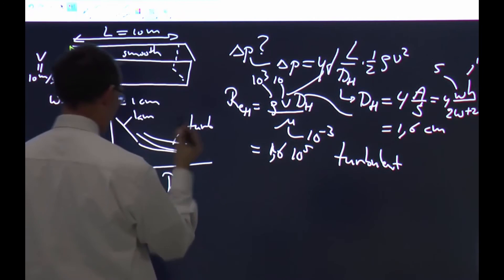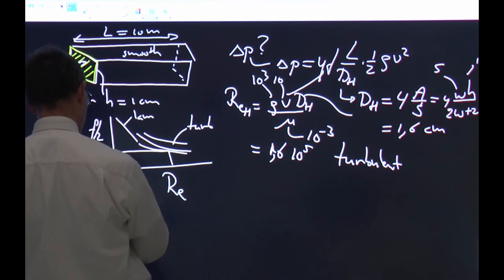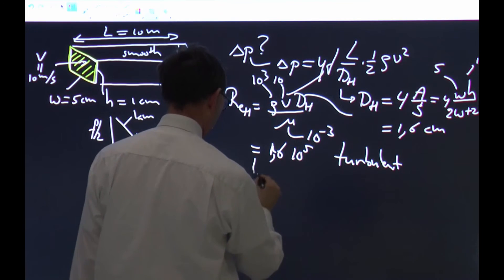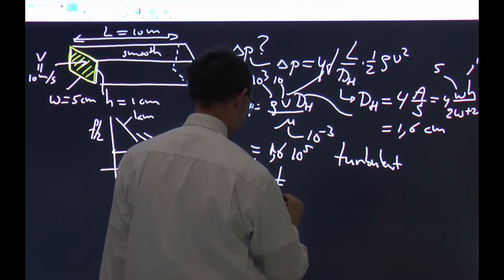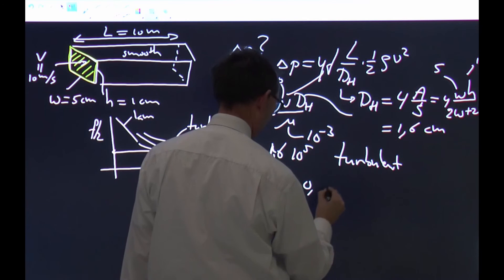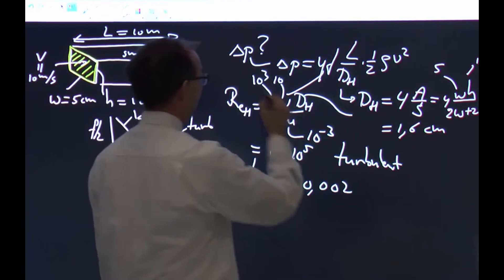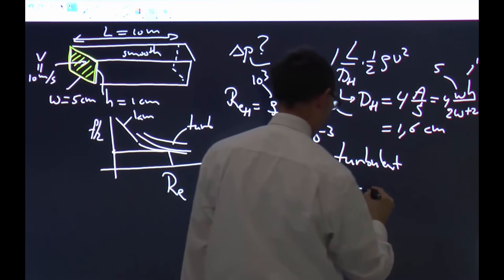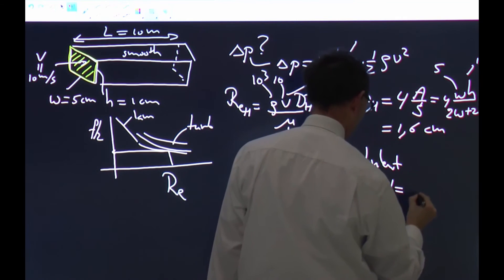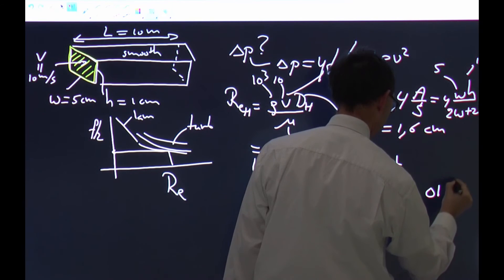We know our Reynolds number, so if you look at the real graph, you can read off, at this Reynolds number, f over 2 is this value, which in this case would give f over 2 equals 0.002, if you read the graph. And thus, we need 4f, 4f equals 0.016.